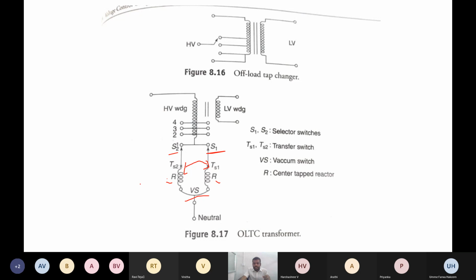And here the center tapped reactors are used. These are tapped at the center, and they are used to increase the impedance. Why are we using the reactors here? Because the reactors are used to increase the impedance of the selector circuit. We have to increase the impedance of the circuit, so for that purpose we are using reactors. This also limits the amount of circulating current. So the main purpose of the reactors here is to increase the impedance and also decrease the amount of current circulating through the different branches.